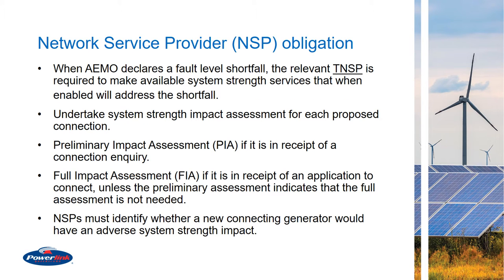NSP obligation. When AEMO declares any system strength gap, it is the TNSP's responsibility to fill that gap as the system strength service provider. It is the NSP's responsibility to undertake system strength impact assessment, PIA, which is the preliminary impact assessment, at the time of the inquiry. If PIA concludes that FIA is needed, which is the full impact assessment, then the NSP is required to undertake the full impact assessment at the time of the application. The NSP must also conclude if a particular generator connection has any adverse impact or not.